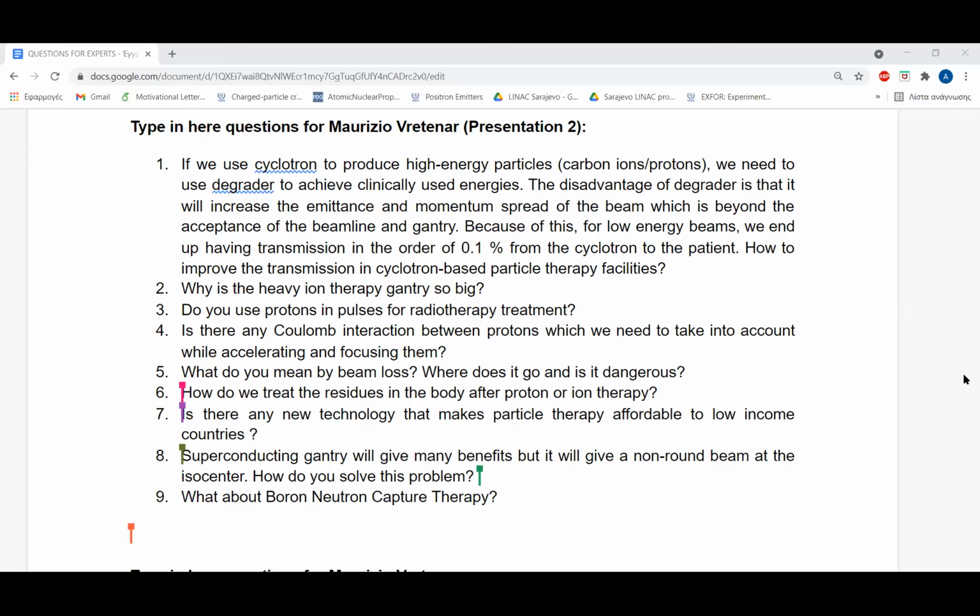The problem is the transmission between the exit of the cyclotron and the patient. And I don't have solutions. This is really a limitation of the cyclotron, in the sense that we always want to treat tumors at different depths, to scan different depths. To scan depths, we have to scan energy, because of the Bragg peak, depth translates into energy. And there is no way in a cyclotron to change the energy inside the machine. There is no button to change the energy.